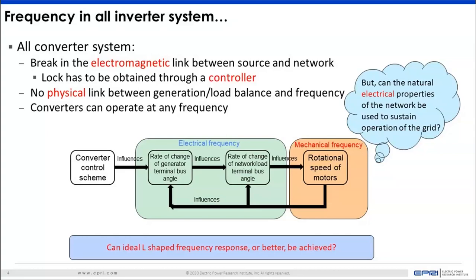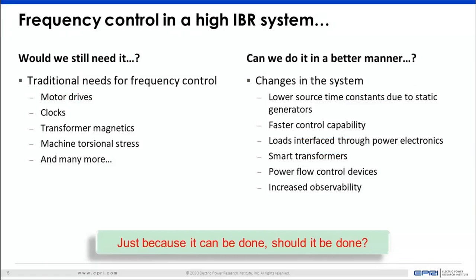So if we have that, can we go towards an ideal L-shaped response, where, upon occurrence of an event, if all the inverter-based resources are reacting, the frequency will settle at a value which is good for the system almost instantaneously? Now, this brings up a philosophical question first: would we still need frequency control in such a system? Would we still have to have a resource which is monitoring and maintaining frequency at the value at which we have grown accustomed to, even though you lose that direct link?